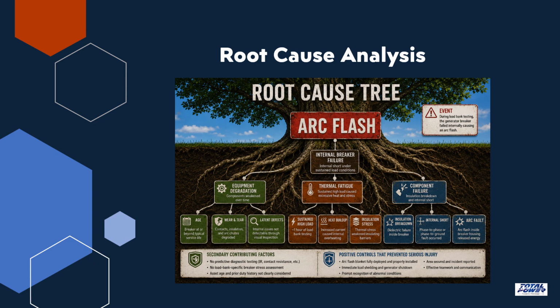Investigators determined the breaker experienced an internal electrical short while operating under sustained load. The failure was not caused by technician error. Instead, the breaker likely contained degraded internal components that could not be identified through normal visual inspections. During approximately 1 hour of high-current load bank testing, thermal stress increased inside the breaker. Eventually, an internal dielectric failure occurred. That failure produced an arc fault inside the breaker housing.